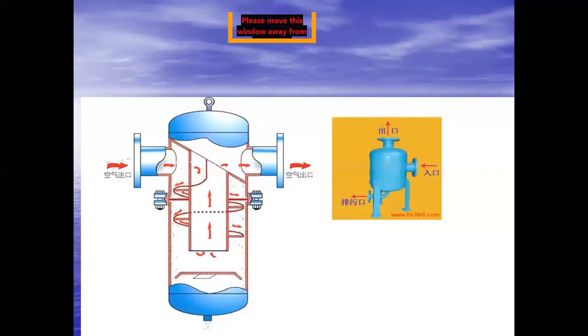One thing, it collects a lot of dirt due to the internal corrosion of the steam pipes. So you may have very, very small rust particles floating around with the steam. Also, the steam may have condensed water. So if your steam has got condensed water, it's sent to this steam cyclone separator. Cyclone separator is quite similar to your cyclone lube oil separator, which is fitted on the side of a generator. Basically, the force of the steam itself causes the steam to turn around, change direction very rapidly.